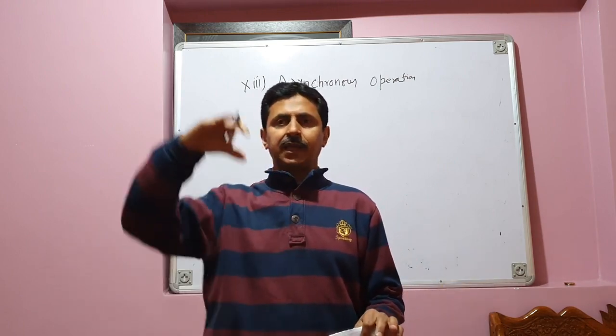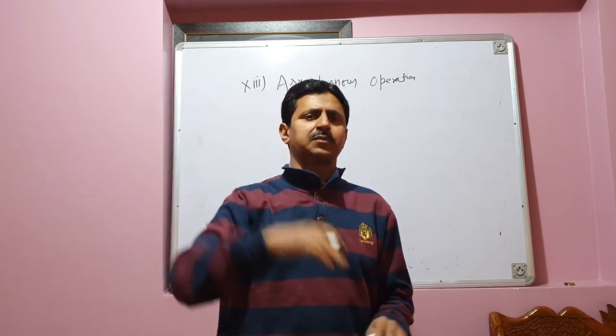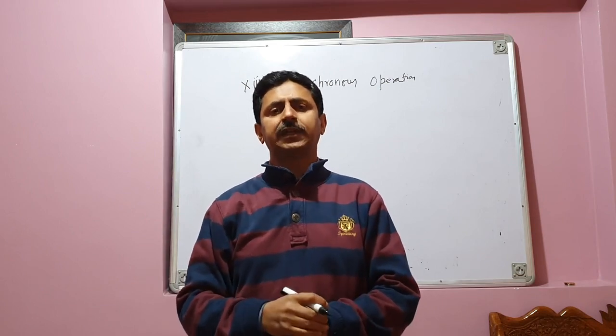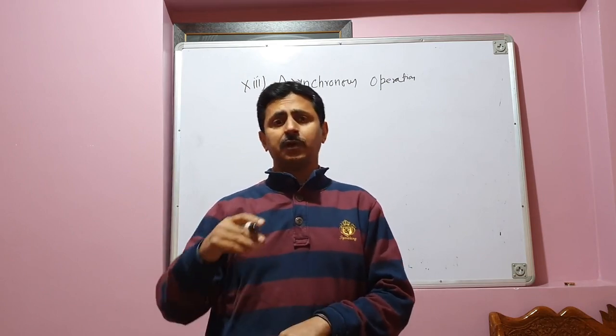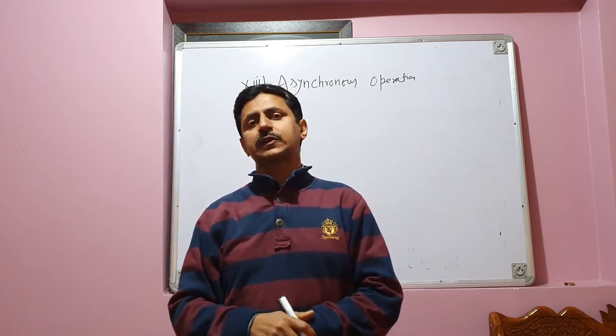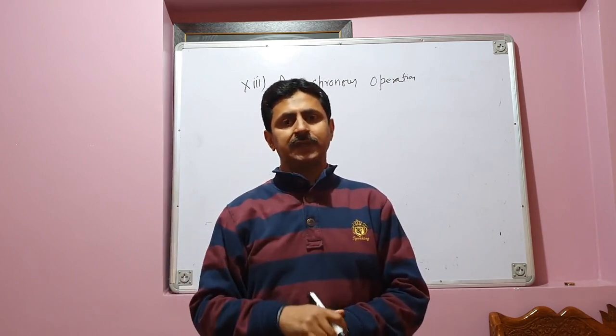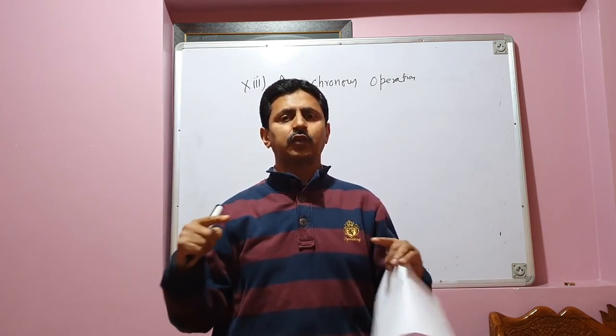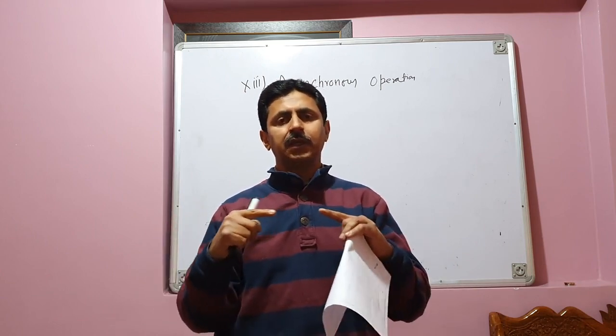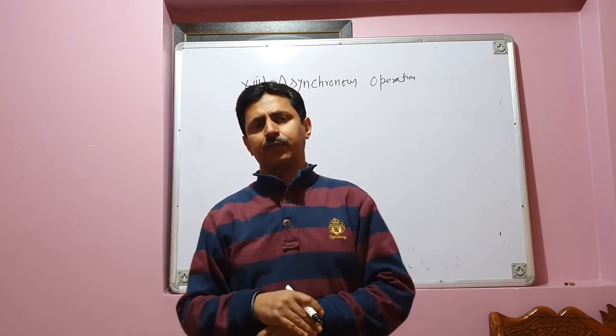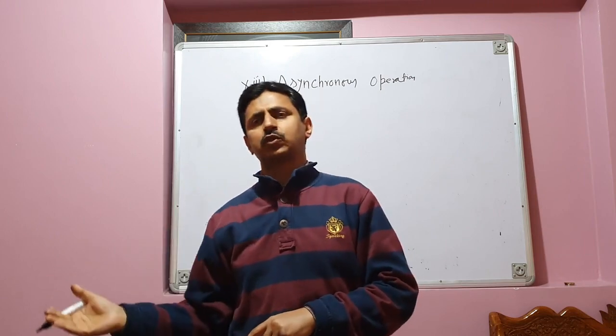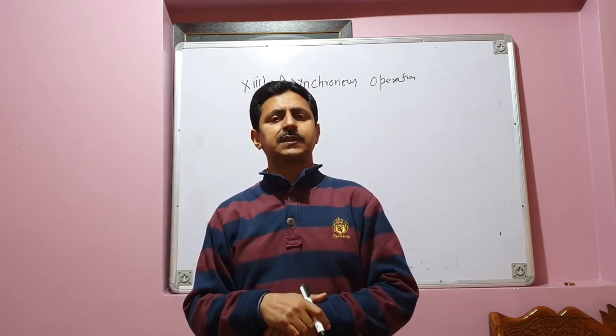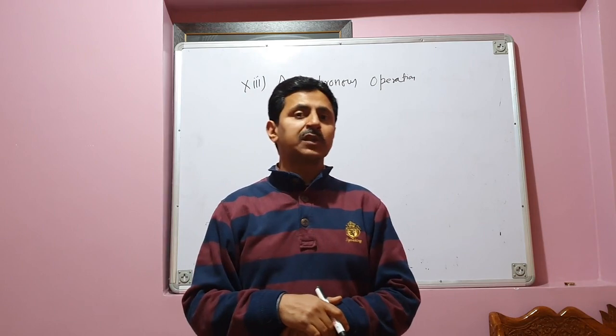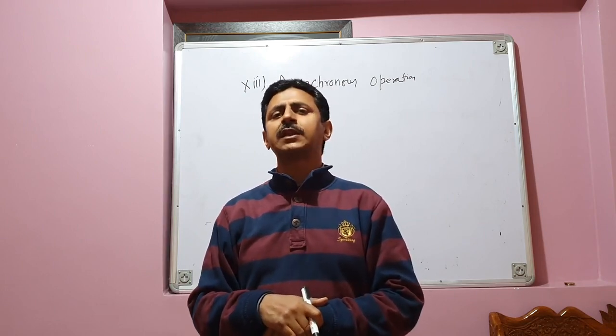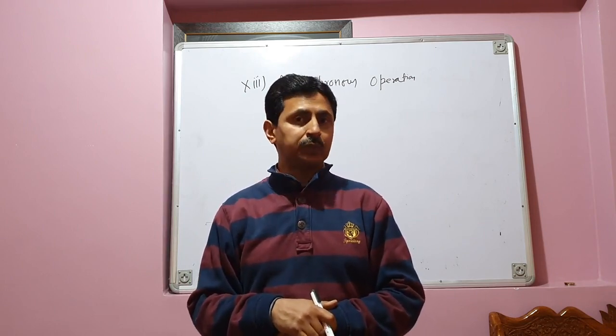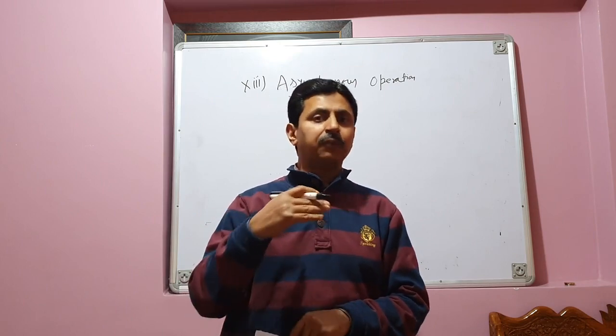At a grid substation, the various transmission lines are synchronized together. They are synchronized in terms of phase sequence. They are also synchronized in terms of the frequency. When various systems are connected together, say 50 hertz systems, all systems must be at the same frequency, 50 hertz, or all systems should be at the same frequency, say 60 hertz. Is it possible to synchronize a 50 hertz system with a 60 hertz system? The answer is no. We cannot synchronize a 50 hertz system with a 60 hertz system.